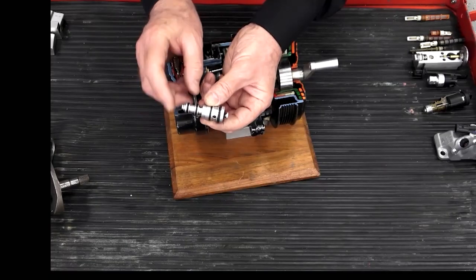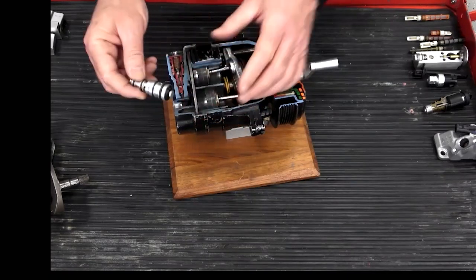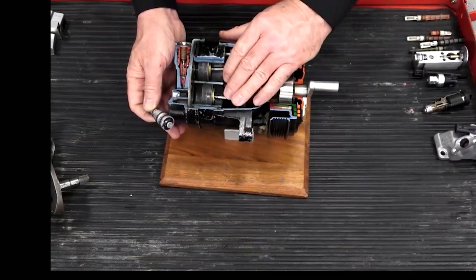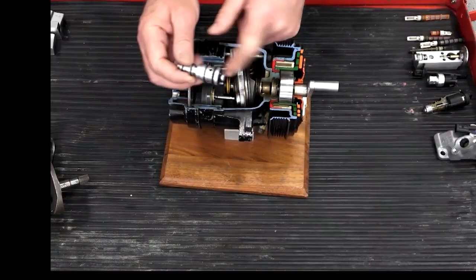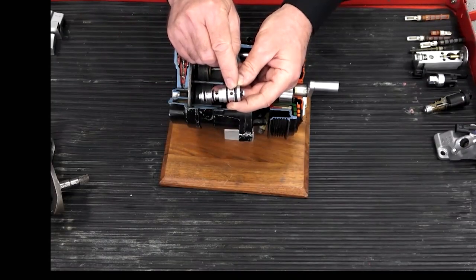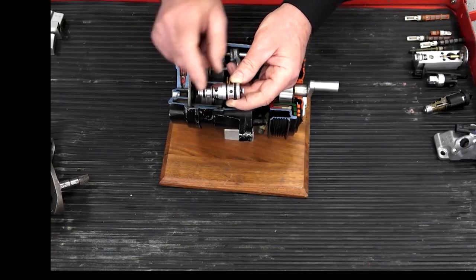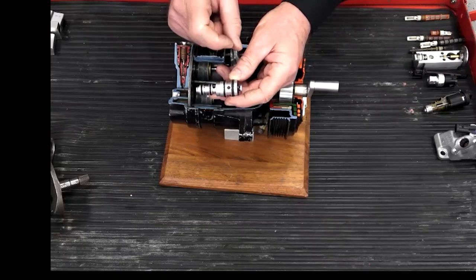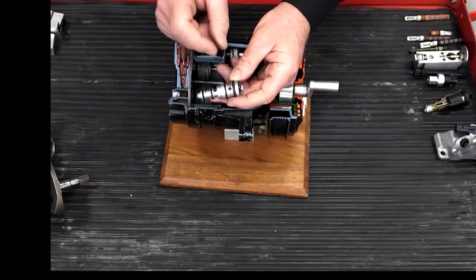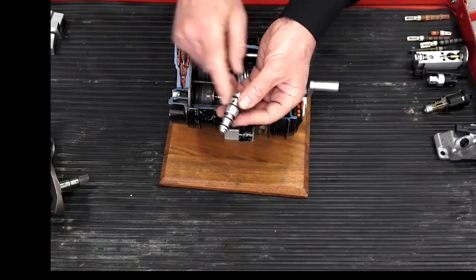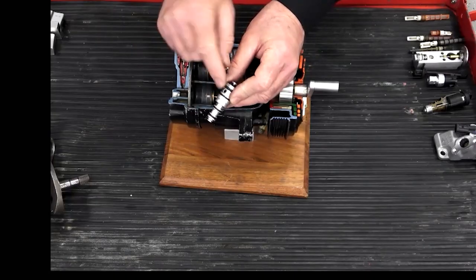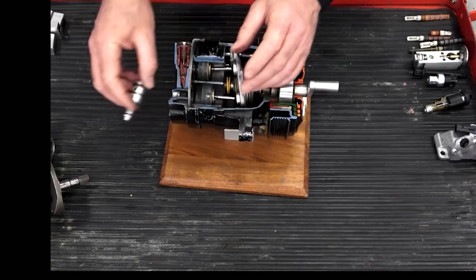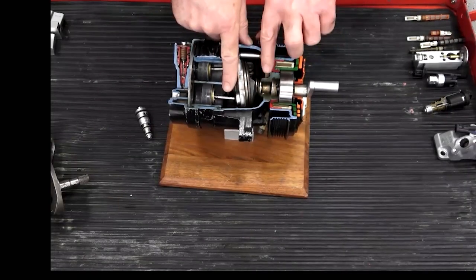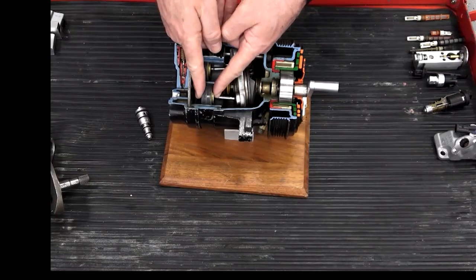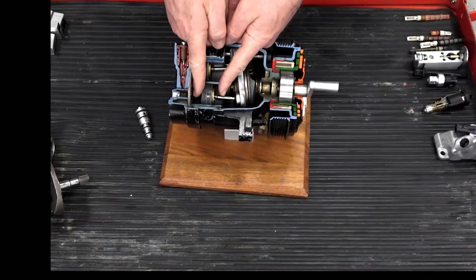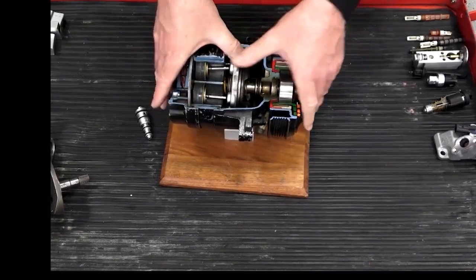This area here is exposed to high side pressure. The area in the center is open to the crankcase of the compressor, the area behind the pistons. And this area here, if you could look very closely inside, you may be able to see a pneumatic bellows attached to a rod. So if the suction pressure increases, it's going to compress the bellows and retract the rod. As the rod moves back and forth, depending on whether we increase or decrease the pressure on the bellows, we can bleed more or less pressure into the crankcase, into the area behind the pistons. And so if I change the pressure drop between the top and the bottom of the piston, in that way I can change the angle of that swash plate.